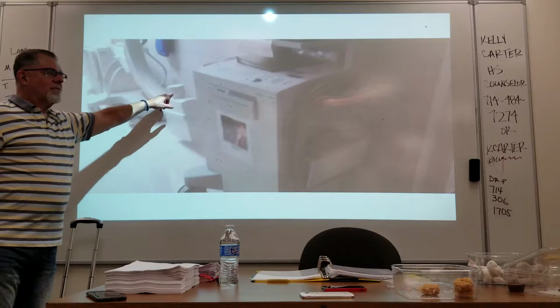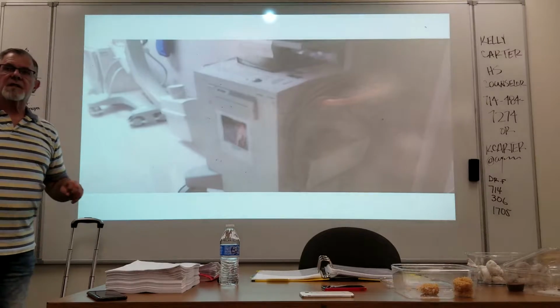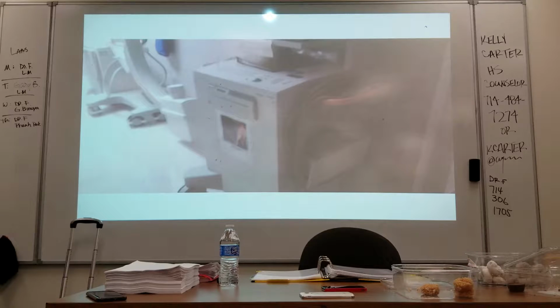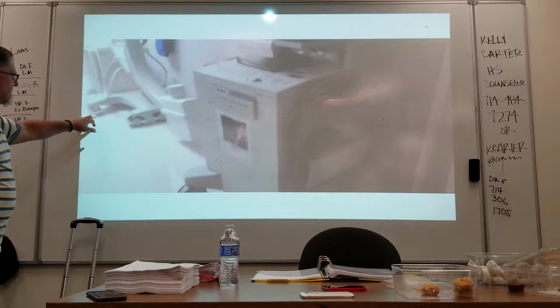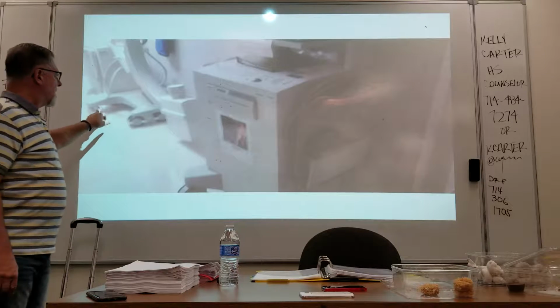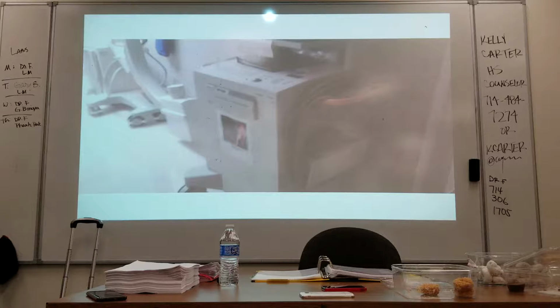So that was a ruling the state made, what, 15, 20 years ago. The problem with leaving it off is they can permanently require you to attach those. So if you're a consistent violator of putting these back on, your facility may be ordered to permanently affix them, which then means that unit would no longer be possible to be used for certain surgical applications. It's not really seen here, but there are brakes on wheels. Those are manual brakes. We'll go through some other things. So that's basically the kind of system.